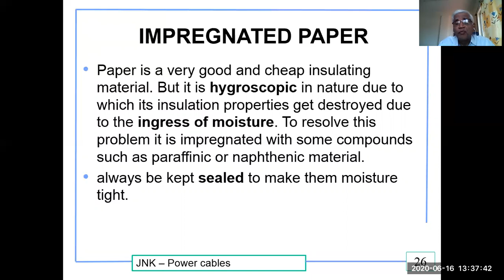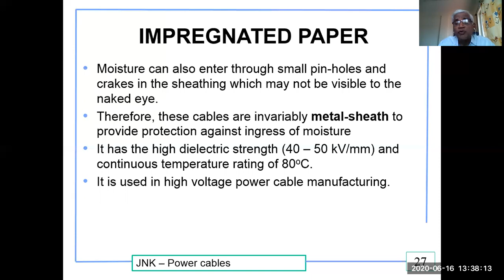Moisture can also enter through small pinholes and cracks in the sheathing, which may not be visible to the naked eye. Therefore, these cables are invariably metal sheathed to provide protection against the ingress of moisture. It has a high dielectric strength, 40 to 50 kV per millimeter, and a continuous temperature rating of 80 degrees centigrade. This impregnated paper is used in high voltage power cable manufacturing.